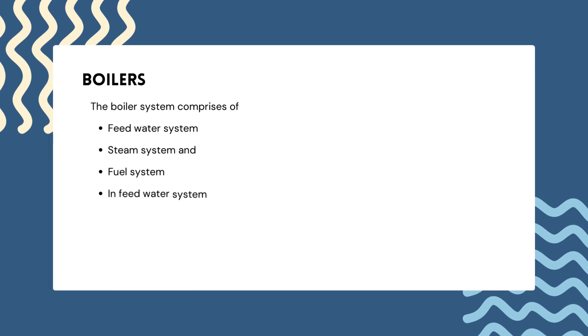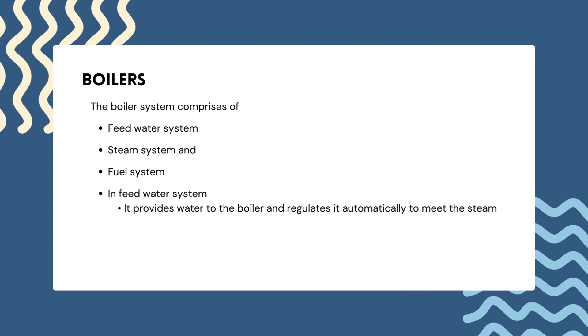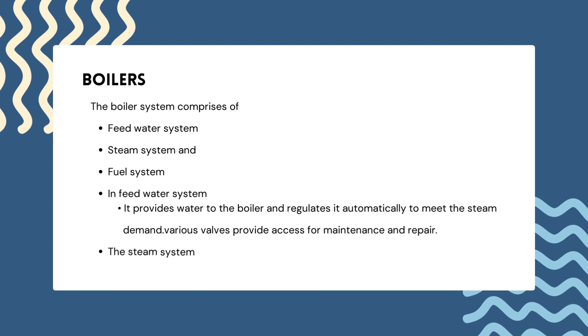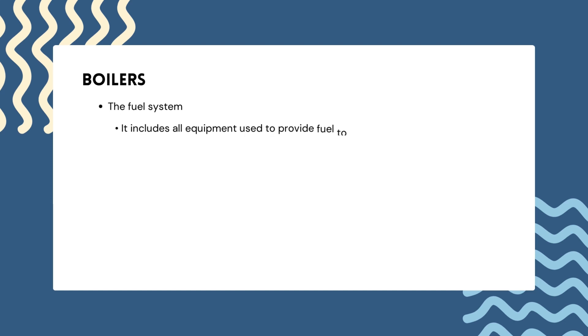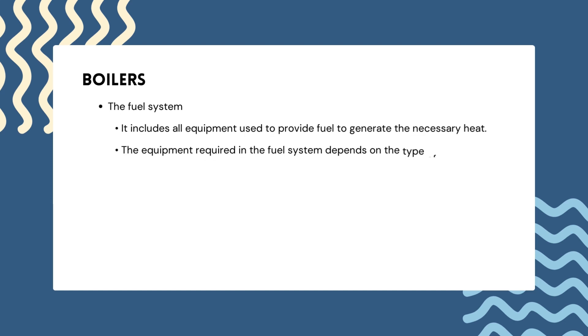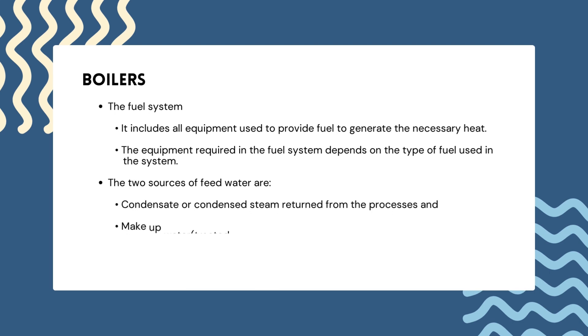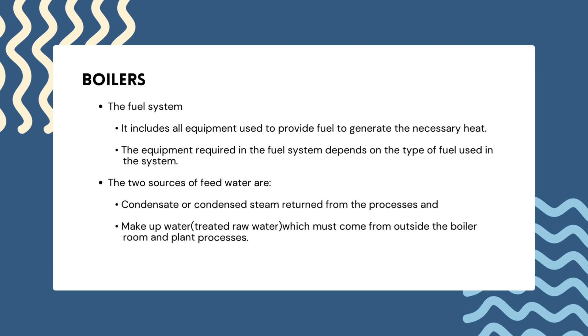The boiler system comprises a feed water system, steam system and fuel system. The feed water system provides water to the boiler and regulates it automatically to meet steam demand. The steam system collects and controls the steam produced in the boiler, directing it through piping to the point of use. The fuel system includes all equipment used to provide fuel to generate the necessary heat. The two sources of feed water are condensate returned from processes and makeup water treated from outside the plant.